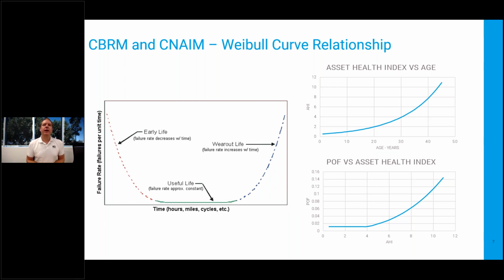Here's an example of a Weibull failure curve. On the right, we've split it out -- the Weibull failure curve relates time on the x-axis to the probability of failure, or failure rate, on the y-axis. We're not really interested in the early life of the asset for asset management purposes, but rather its end of life. So for mathematical simplicity, we simplify the curve and make the 0 to 4 health index to POF relationship linear and flat, ignoring those early-life failures, which are largely manufacturing and installation defects.